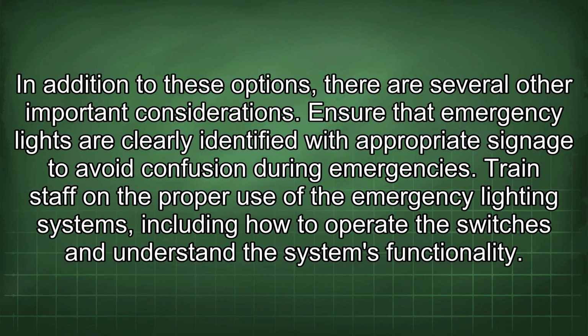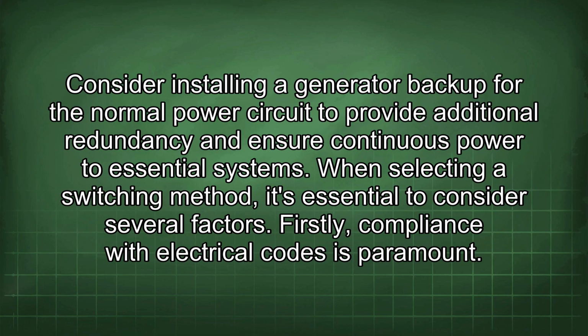In addition to these options, there are several other important considerations. Ensure that emergency lights are clearly identified with appropriate signage to avoid confusion during emergencies. Train staff on the proper use of the emergency lighting systems, including how to operate the switches and understand the system's functionality. Consider installing a generator backup for the normal power circuit to provide additional redundancy and ensure continuous power to essential systems. When selecting a switching method, it's essential to consider several factors.